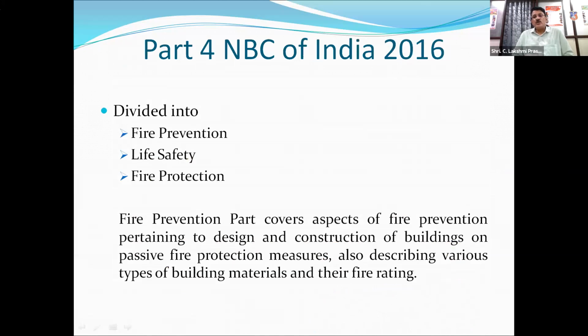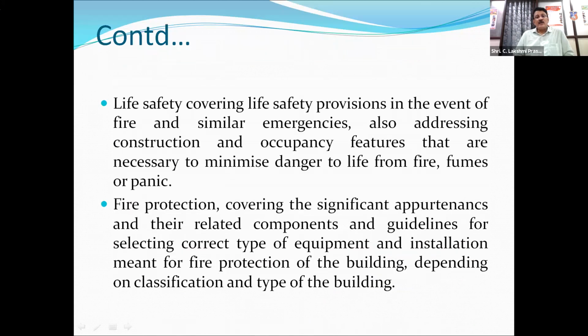Then Part 4 of the NBC of India is divided into three parts: fire prevention, life safety, and fire protection. The fire prevention part covers aspects pertaining to design and construction of buildings and passive fire protection measures, also describing various types of building materials and their fire rating. Life safety covers life safety provisions in the event of fire and similar emergencies, also addressing construction and occupancy features necessary to minimize danger to life from fire, fumes, or panic. Fire protection basically covers the active fire protection systems, like the hydrant system, sprinkler system, fire pumps, and hose reels. The alarm system comes under life safety.